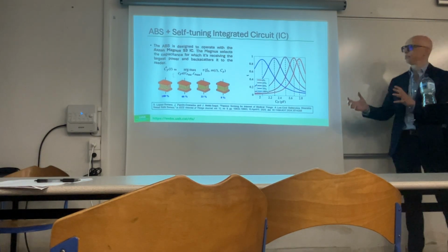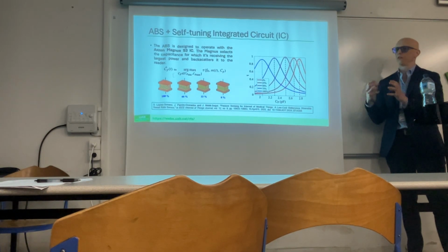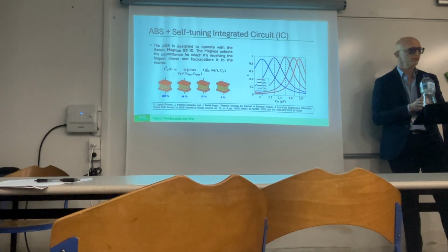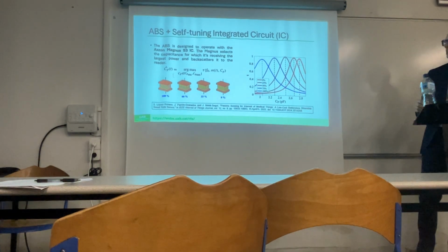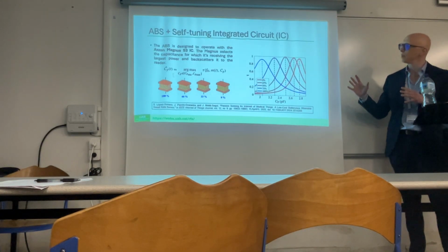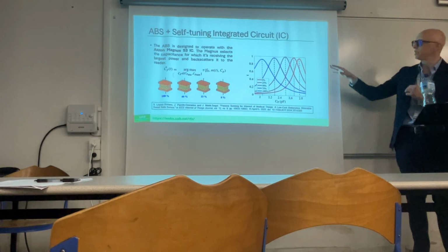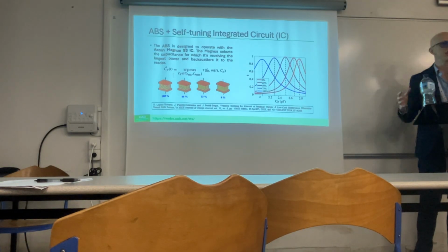So now we know how the dielectric properties of the absorbent change depending on the amount of liquid that is in the absorbent. And here I'm going to show how the self-tuning integrated circuit tracks the variations in the input impedance.